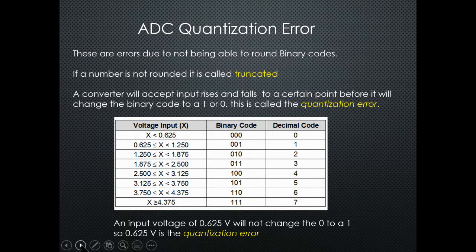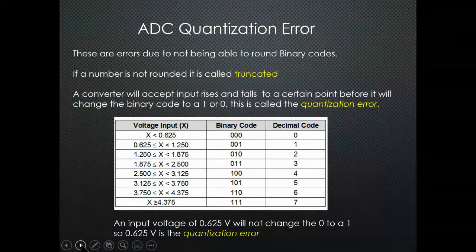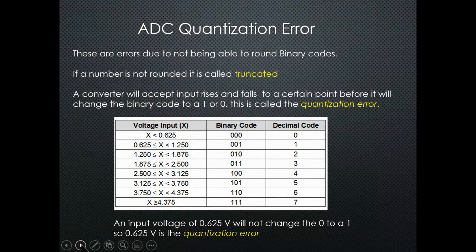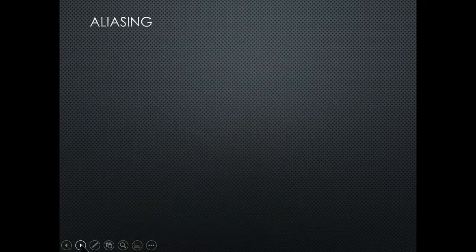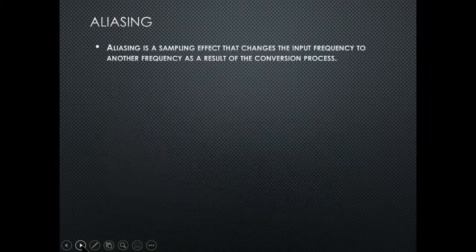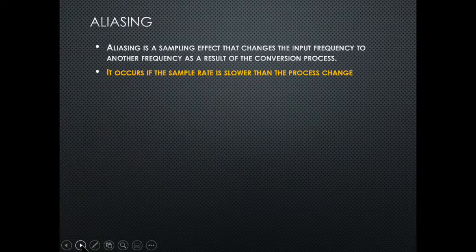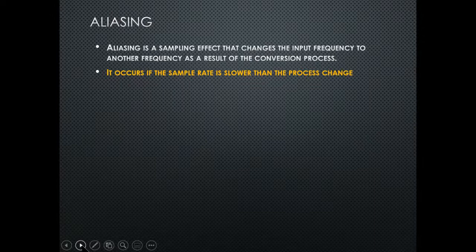An input voltage of 0.625 volts will not change to a one — 0.625 volts is the quantization error. Aliasing is a sampling effect that changes the input frequency to another frequency as a result of the conversion process. It occurs when the sample rate is slower than the process change — if the signal from the transmitter changes faster than you're scanning, you miss some of those analog signals.